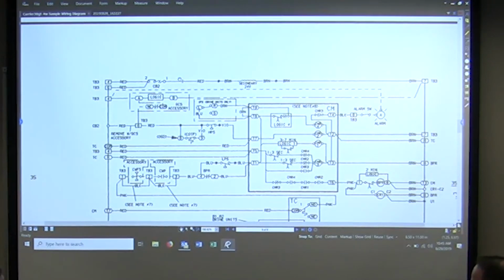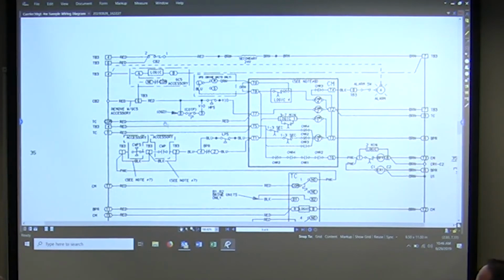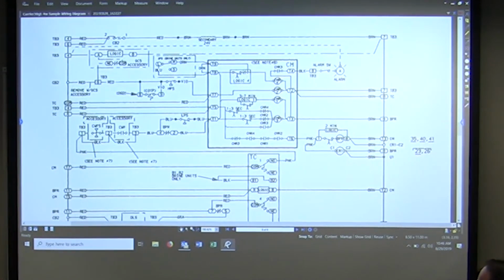Because it's brown, right? Okay. Yeah, because it's brown. See that thing? It says COM there. Brown is brown. Does that mean it's common? I don't know why you'd use COM there because it throws you off, but it's 24 high, right? This is tied into this with the rest of it. So for some reason they've got common there. It's just a common terminal. Yeah, and maybe that's all. Terminal 4 right now. You can see there's a 4 here, 4, 4. There may be another down below.